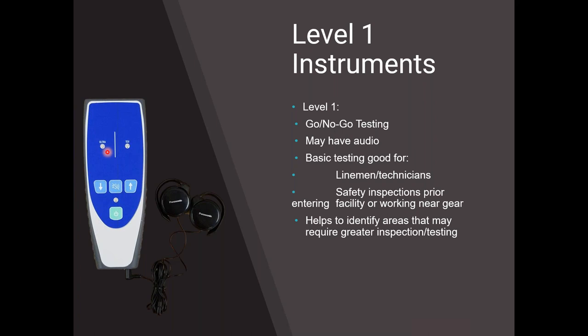If I'm entering a room, if I'm going to be near gear, I can just do a quick 10, 20 second test on the gear from the outside and say, okay, in the area I'm working on, I've got nothing that has any possibility of PD in it. So it's good for safety inspections for entering facilities. It helps identify areas that may need greater inspection and testing. Limitations are you may get false positives. It's just a go, no-go test.